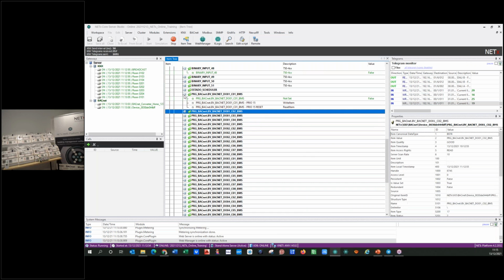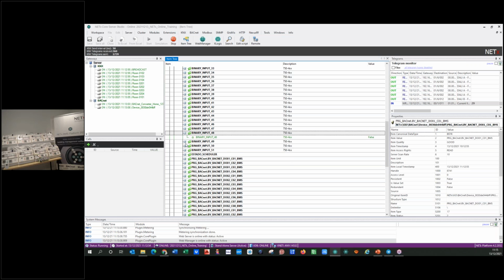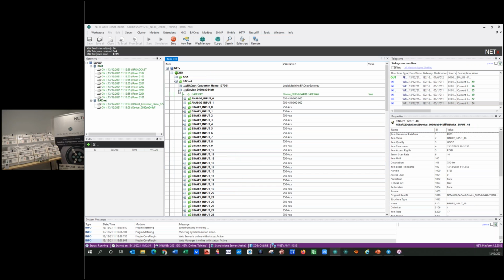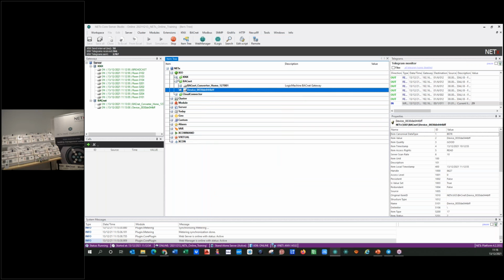And it was really easy to do this because it was just discovering of those elements that are mapped into BACnet. So now, and this is very interesting, we have BACnet and we have KNX, and as we mentioned, this is a tool for integration. One of the most interesting things we can do is the integration, and there is a lot of possibilities now to integrate KNX and BACnet, BACnet to KNX, KNX to BACnet. One of these is using a simple link. This is called a virtual link. It's very easy to do this, and we can do it different ways.